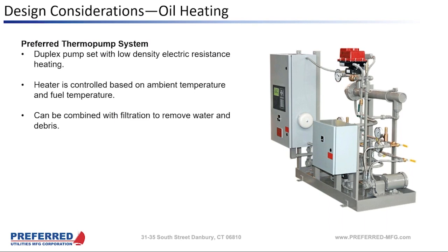It was 14 degrees outside and the job had a lot of overhead exposed piping. My concern was if that oil gelled in the overhead piping, that can clog up the piping and we wouldn't even be able to move it with the Thermopump running. It turns out the system was running and the oil was staying warm, and there's a thermometer on the inlet and the outlet thermometer is showing 52 degrees, which is really, really warm oil when it's 14 degrees outside. It gave me a lot of peace of mind knowing we're generating all this warm oil, and we've probably had 100,000 gallons at this facility being kept warm with a Thermopump system.